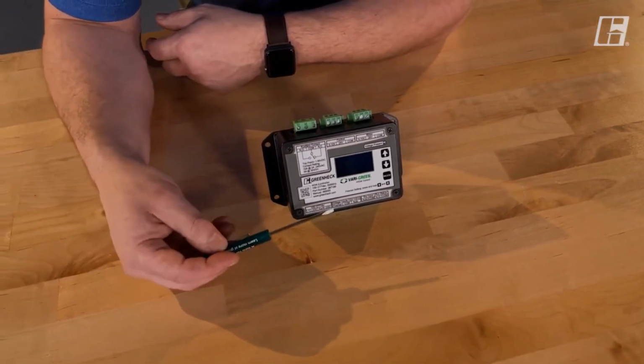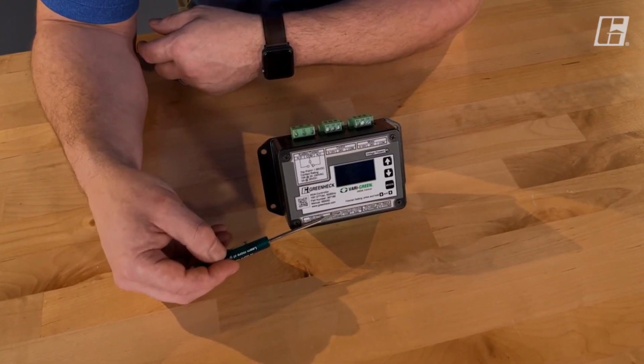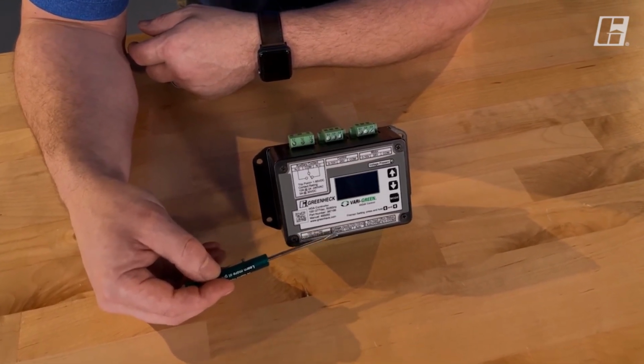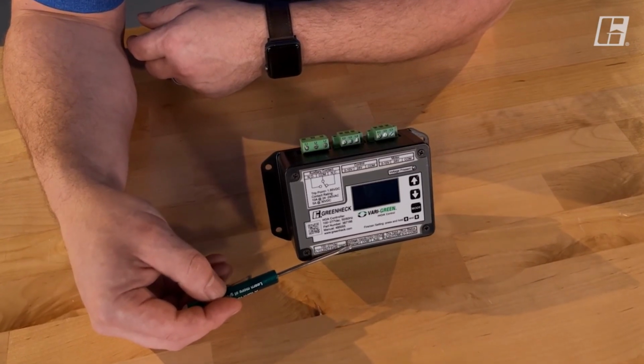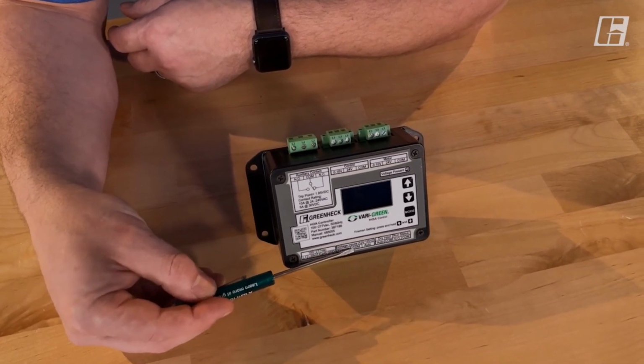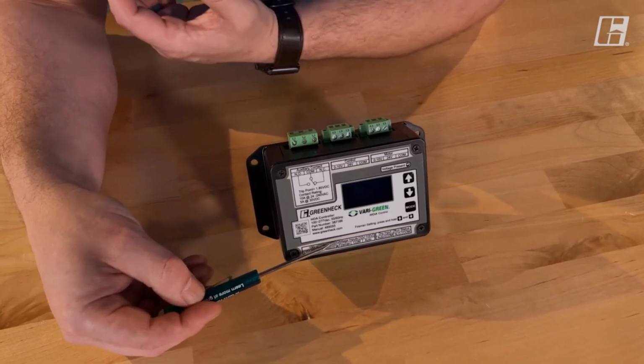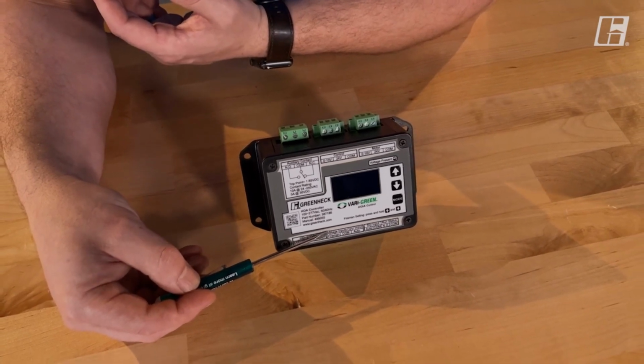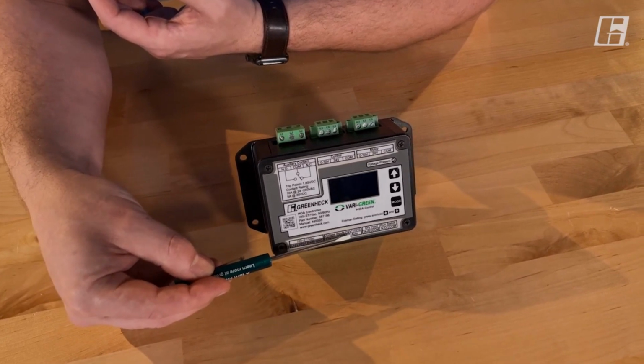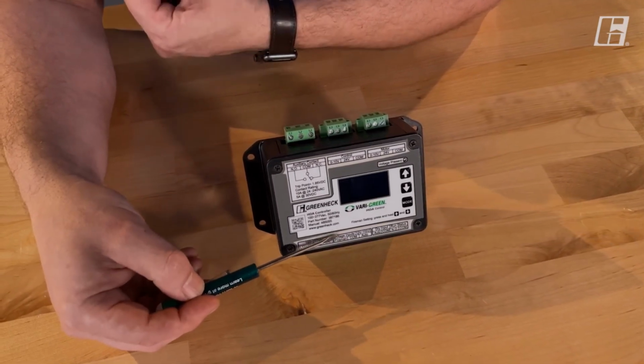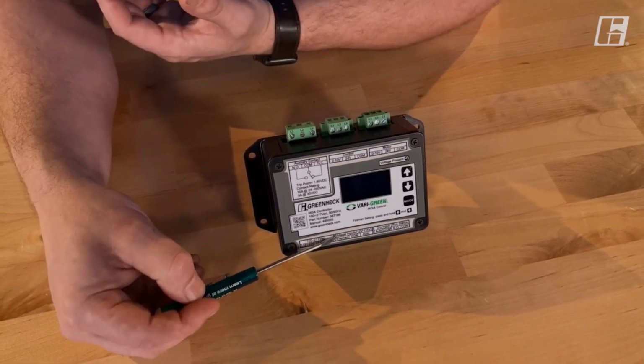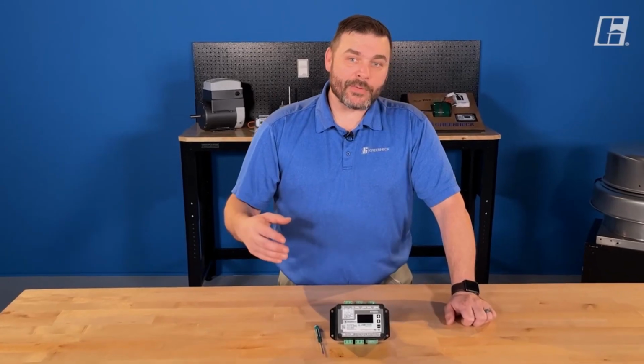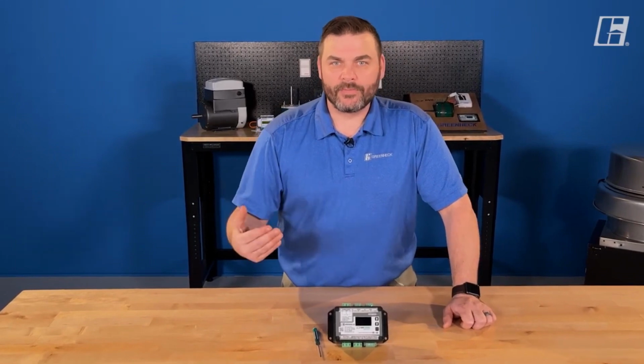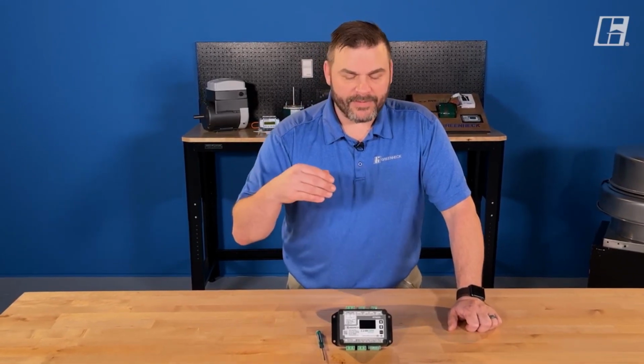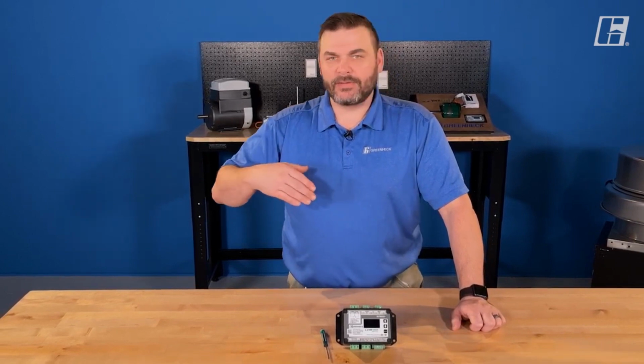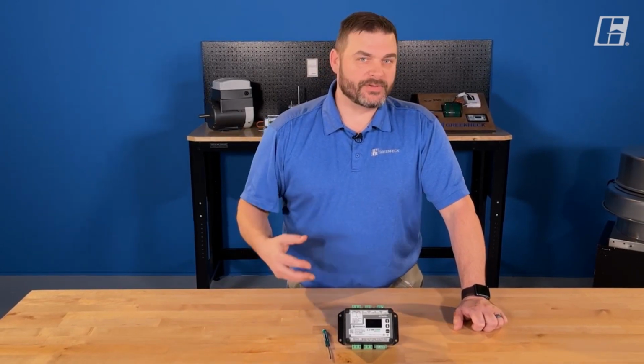Now the last terminal across the bottom, it's labeled fireman's. It is a voltage input, so I would use one wire to the fireman's terminal and one wire to the common. This accepts anything from 12 to 120 volts, just like the voltage input. The only difference here is that this fireman's is really just an override. That fireman's terminal is really a second speed or an override. But here's the key. If it's enacted, it takes precedence over all other modes or operations of this device.